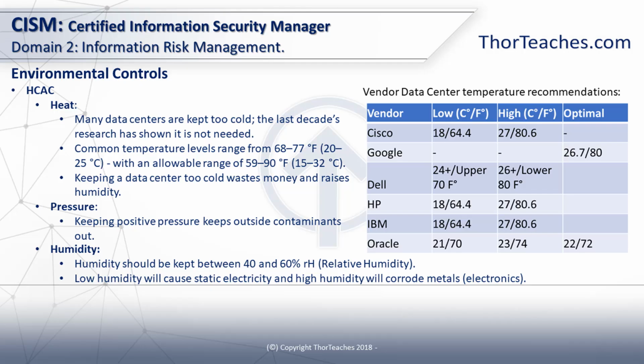Another side effect to keeping it too cold is it's going to raise the humidity levels. We obviously have humidity control in our data center as well. If we keep the temperature unnecessarily low, which then raises humidity, we're also going to expend more power pulling the humidity out of the room. I've been in many data centers where it's kept just around 60 degrees Fahrenheit or 15.5 Celsius or even lower. First off, it's a waste of money to keep it that low. Also, it's miserable to work in for the people who are in the data center.